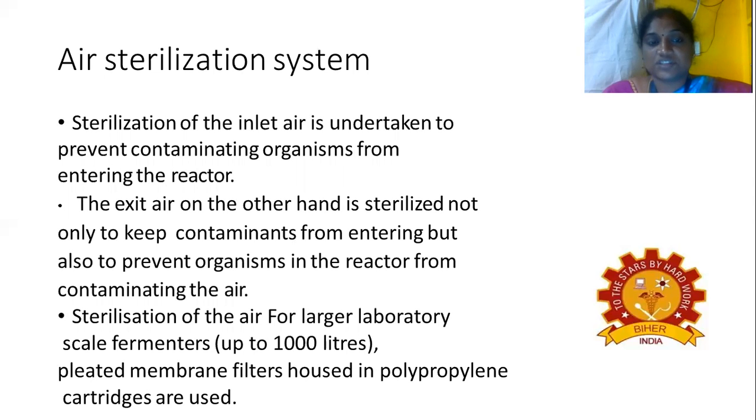Air sterilization system. Sterilization of the inlet air is undertaken to prevent contaminating organisms from entering the reactor. The exit air, on the other hand, is sterilized not only to keep contaminants from entering, but also to prevent organisms in the reactor from contaminating the air. For larger laboratory scale fermenters, up to 1,000 liters, pleated membrane filters housed in polypropylene cartridges are used.